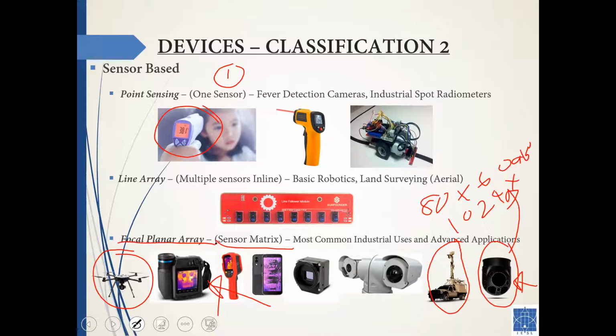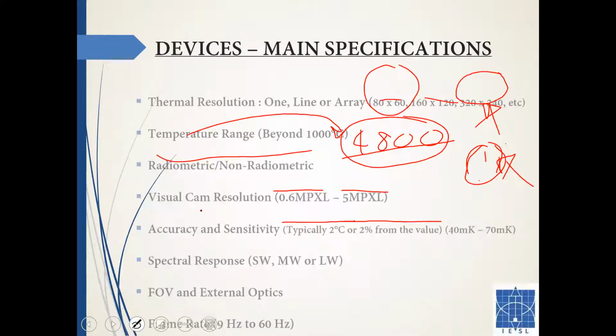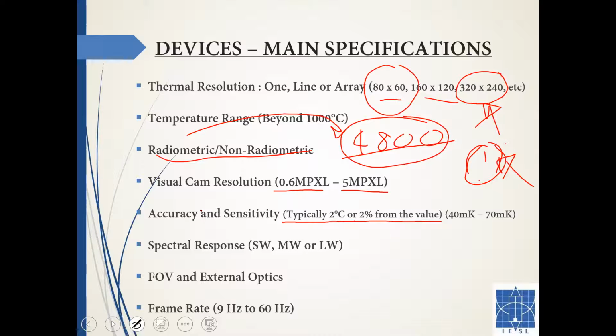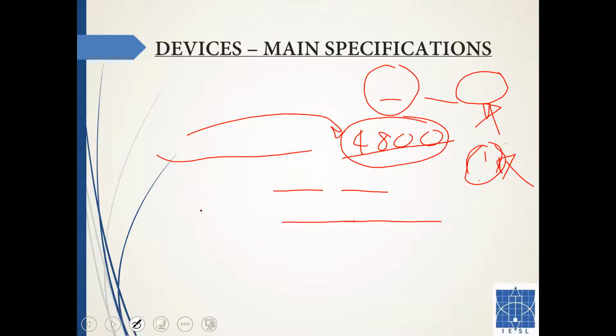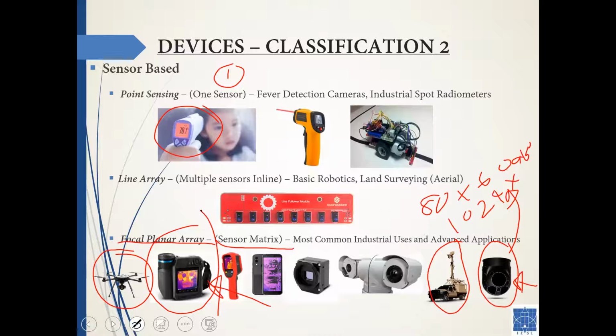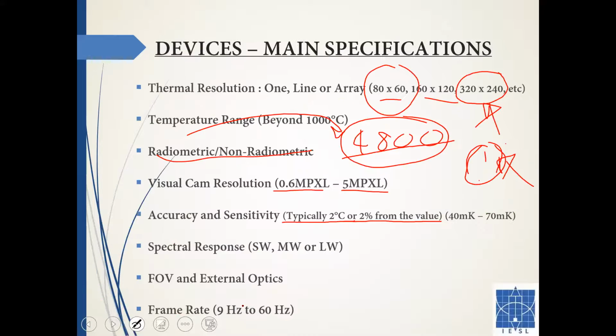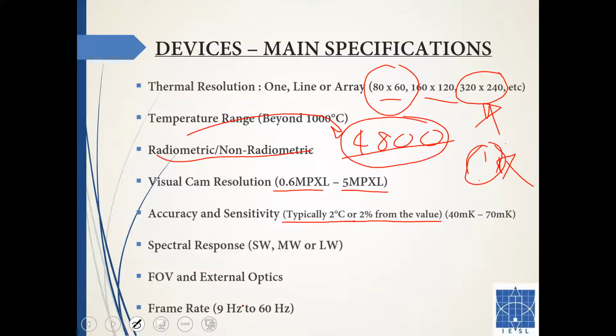So it needs to be pretty accurate. But your focal plane array industrial camera is meant for a different application. You cannot switch, right? So you need to understand before you're selecting the camera. However, recently after this pandemic, they have rolled out a separate firmware for these imagers with the EBT mode, elevated body temperature mode, so that after installing that firmware on this camera, you can carry out EBT measurements. But not for every imager, of course. With these imagers it was rolled out, but for these imagers it was not. They were not sophisticated enough for a firmware update at this point. So you need to look at the specifications. They specifically mention whether EBT mode is enabled or not.